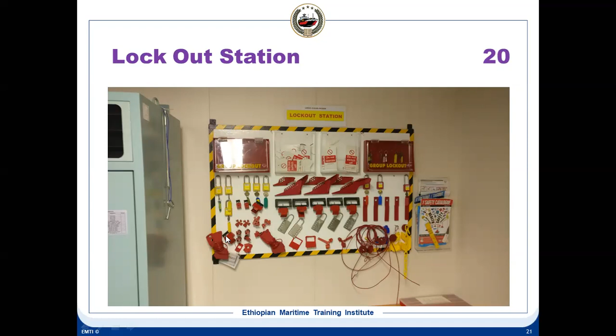So the conclusion is the sequence of isolation. The first is plan the job. That includes prove the equipment dead, switch off, prove the equipment dead, then isolate, lockout for life, permit issued. Once permit is issued, work, then de-isolate. Then permit to test and prove safe, put in service. So the sequence goes like this. Okay.